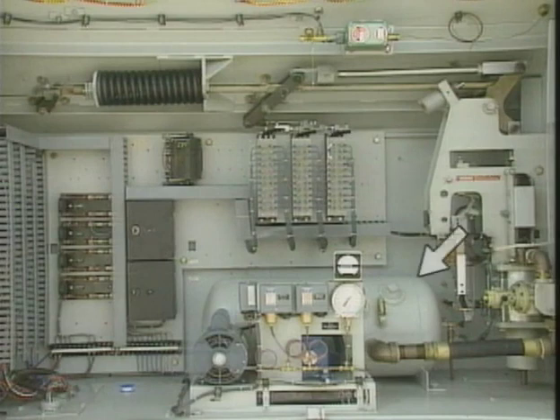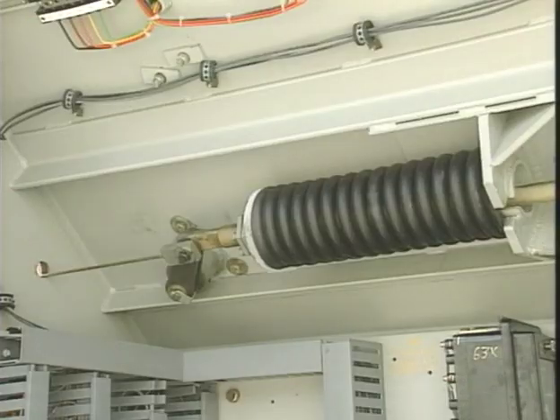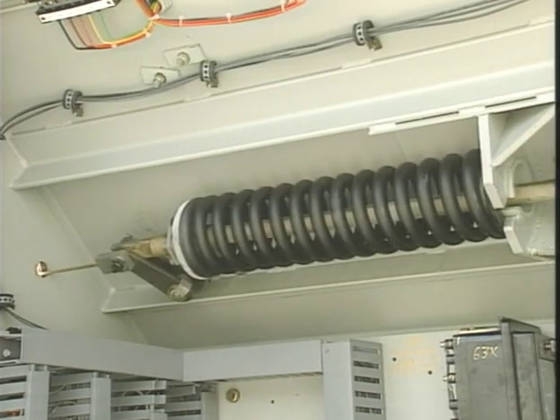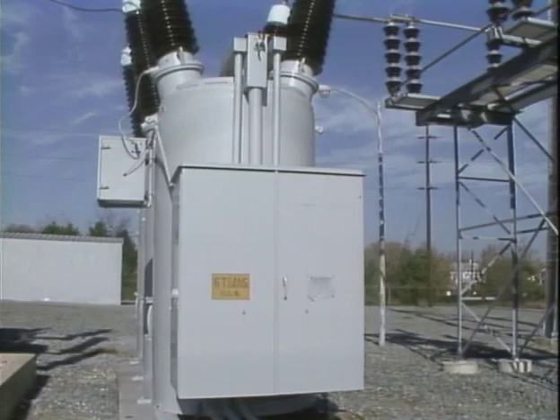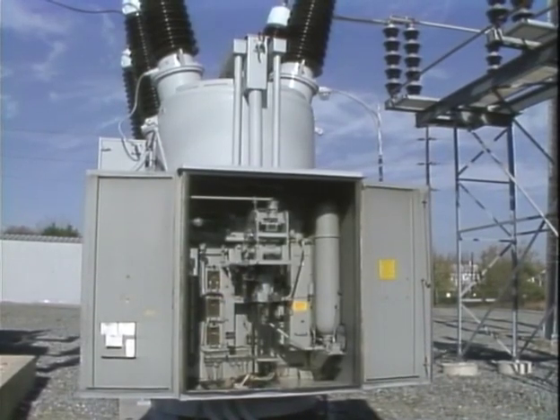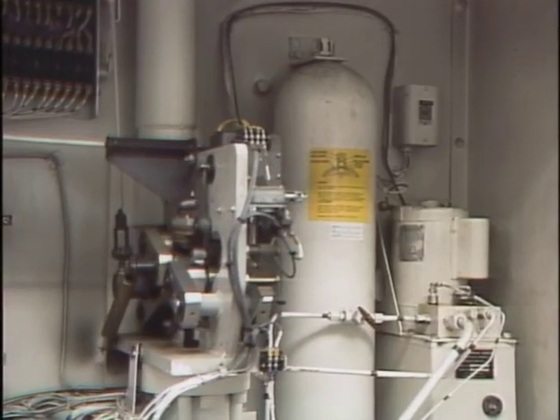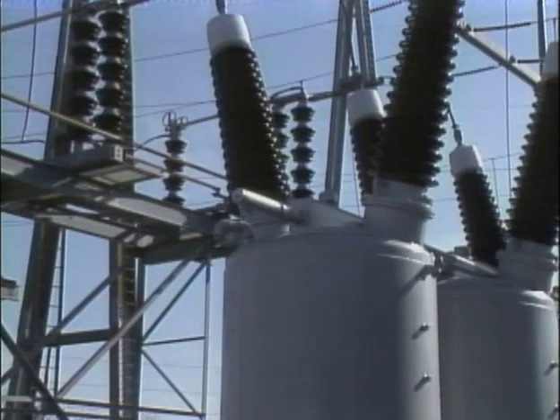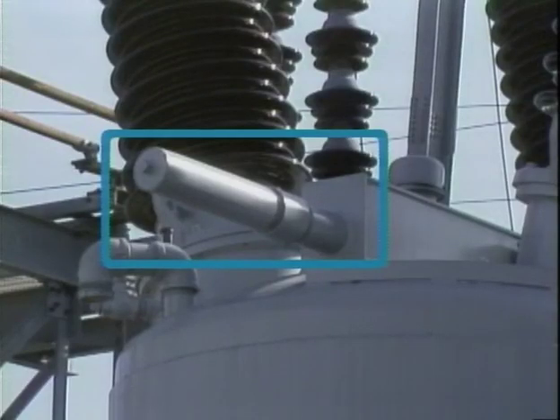With this mechanism, a reservoir of compressed air provides the force needed to close the breaker contacts and at the same time charge an opening spring. The opening spring provides the force needed to open the breaker contacts. A fourth type of operating mechanism is the hydraulic mechanism. With this mechanism, pressurized fluid provides the force to close the breaker contacts and at the same time charge an opening spring. The opening spring, which is enclosed in a cover pipe near the top of the breaker, provides the force needed to open the breaker contacts.